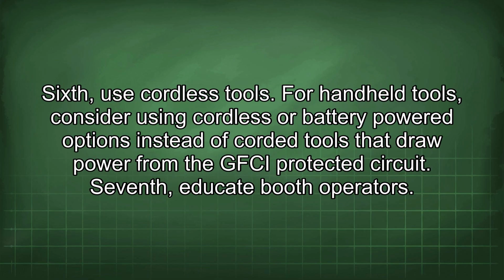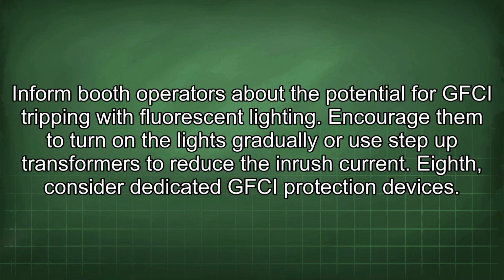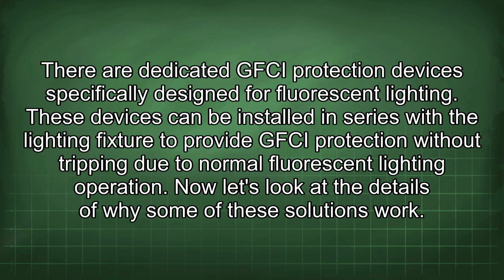Sixth, use cordless tools. For handheld tools, consider using cordless or battery-powered options instead of corded tools that draw power from the GFCI protected circuit. Seventh, educate booth operators. Inform booth operators about the potential for GFCI tripping with fluorescent lighting. Encourage them to turn on the lights gradually or use step-up transformers to reduce the inrush current. Eighth, consider dedicated GFCI protection devices. There are dedicated GFCI protection devices specifically designed for fluorescent lighting. These devices can be installed in series with the lighting fixture to provide GFCI protection without tripping due to normal fluorescent lighting operation. Now let's look at the details of why some of these solutions work.